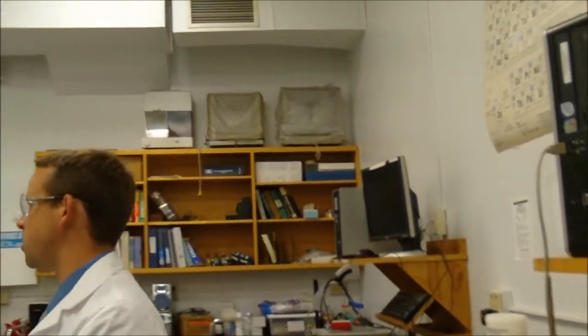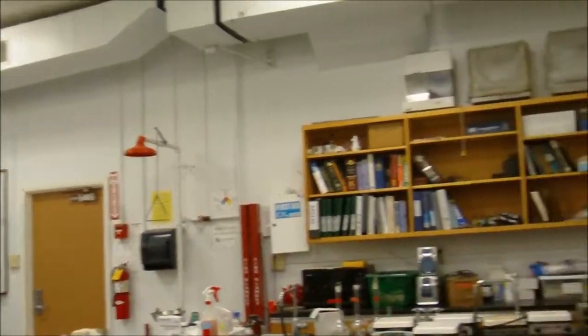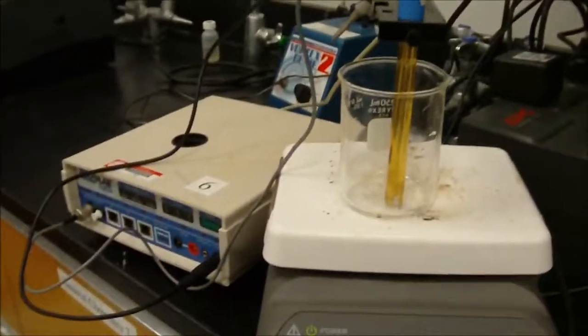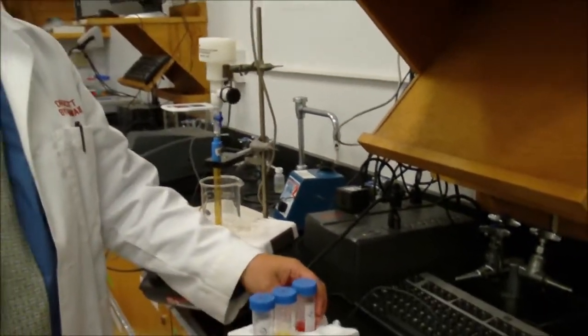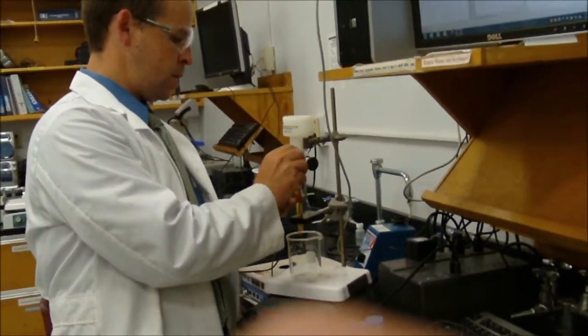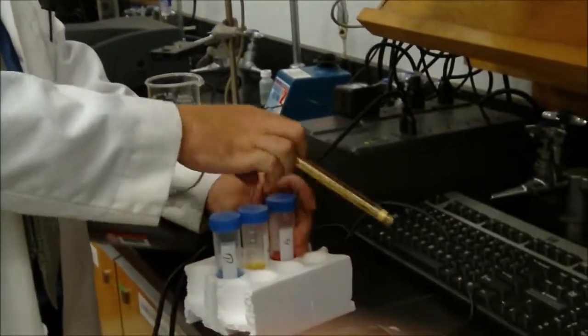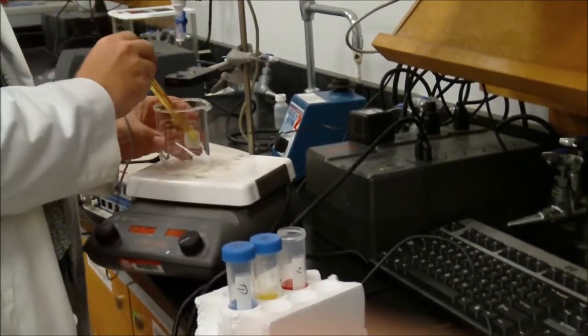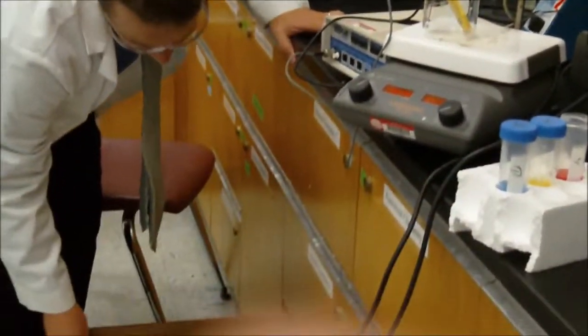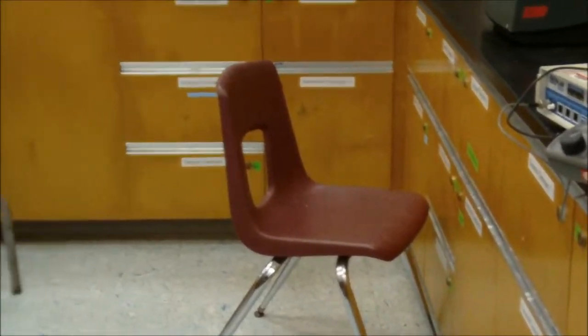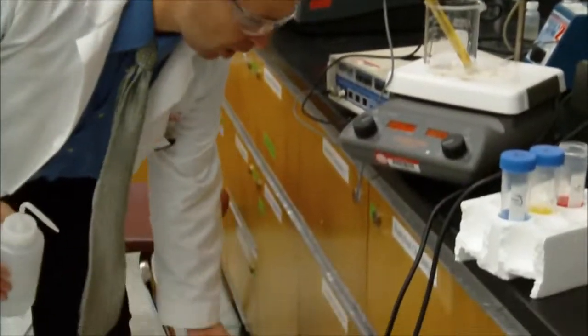Now it is measuring the pH, hopefully the pH of nothing right now, so I have to get 3 buffers, pH 4, 7, and 10, and tell the pH meter what the pH of those buffers is. Here I have my 3 buffers, pH 4, pH 7, pH 10. I have the lids labeled as well so I don't mix up the lids on the buffers. I can take this pH probe here and put it in pH 4 solution. Before I put it in there though, I want to make sure I have my rinse bottle and I want to rinse off. Here I have a rinse bottle with deionized water. I'm going to get a waste bottle too.